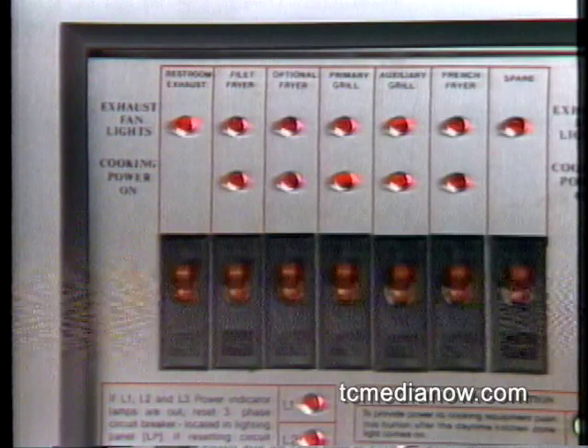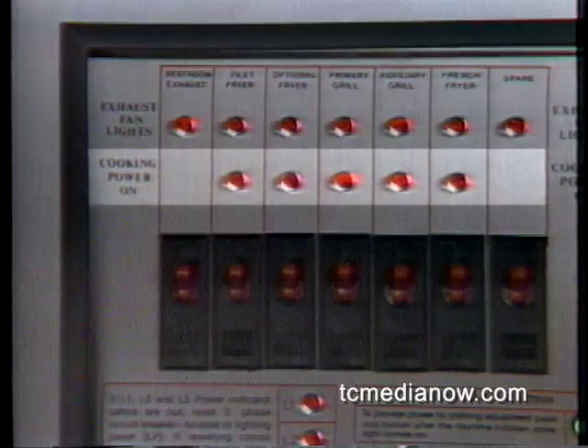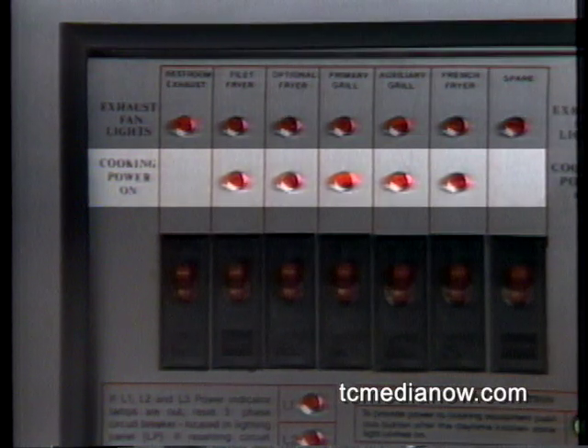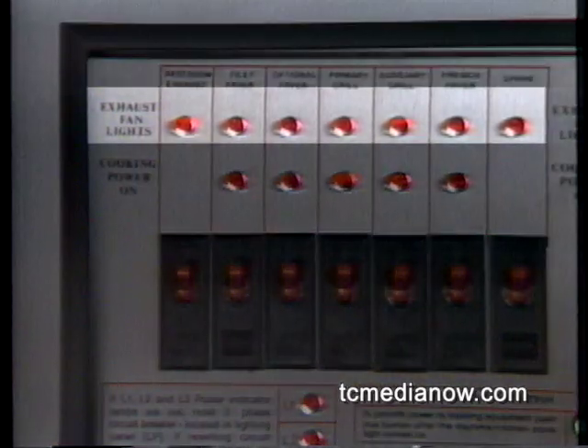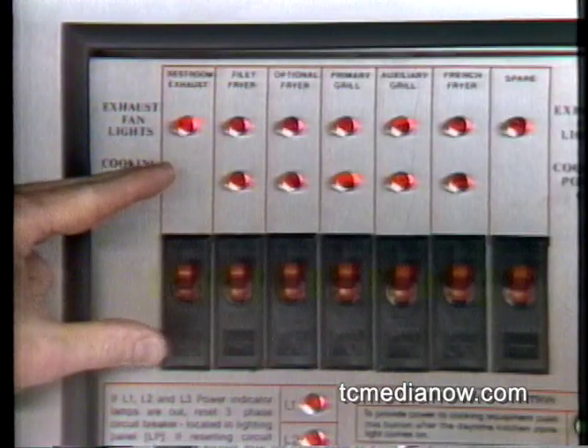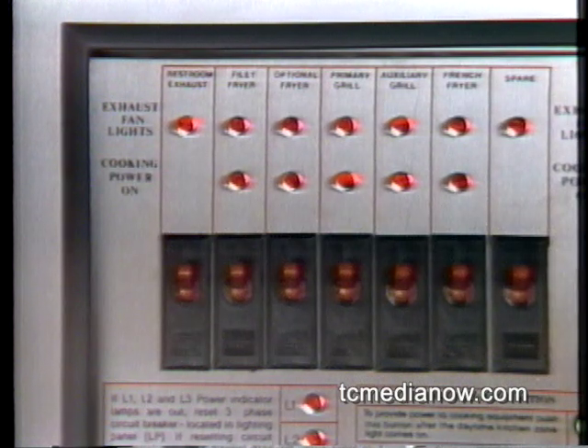Each energy interlock system panel also has an array of status lights that show the condition of circuits connected through the system. This row of lights shows the status of circuits to the cooking equipment, and these lights show the status of circuits to exhaust fans. If a cooking equipment unit should fail to operate while the energy interlock system is in the daytime mode, check this bottom row of lights to see if the corresponding circuit light is lit. If the light is lit, it means that the energy interlock panel is providing power to the power outlet for that cooking unit. The trouble is not with the interlock system, but with the cooking unit itself.